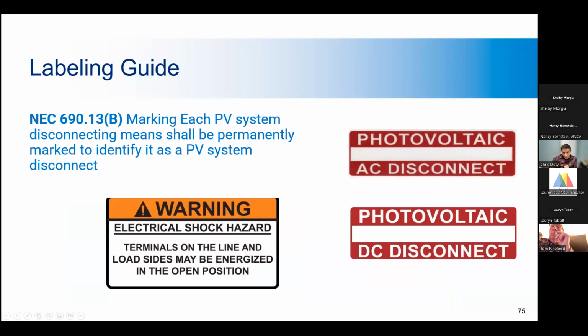All right, so next, the NEC requires these markings on PV system disconnects, depending on the disconnect you have. If it's AC, you would have this one. If it's DC, you would have this one. Traditionally, if you shut off the disconnect to a system, the power will be off. But if you shut down the main disconnect and not the solar disconnect, if the sun's out, it's entirely possible the system will still be energized. If you have a load side connection, it's very important to make this clear. And so remember that the labels have to be suitable for the environment they're installed in, and the labels should be expected to last the life of the system.